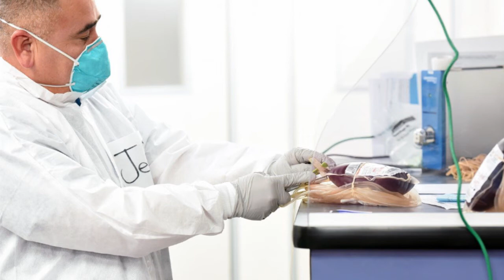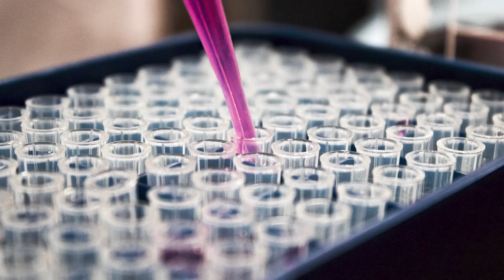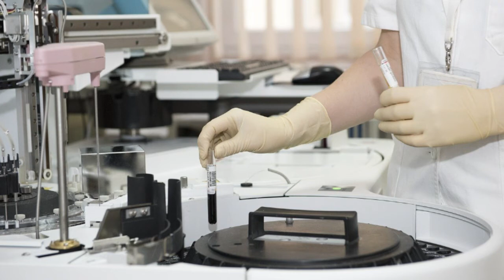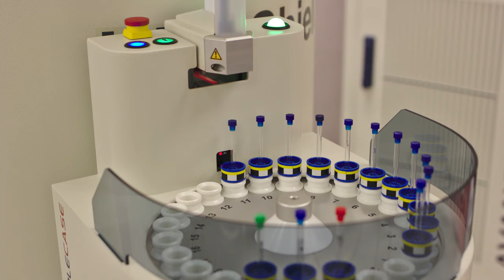Now many of the reagents are based on antigen-antibody reactions. Reagent storage temperature is very important. Frequent thawing and freezing decrease the potency of antigens and antibodies. Onboard reagent stability. The open reagents and loaded reagents in the instruments have very short stability as they are exposed to atmospheric air and frequent pipetting by manual method or the reagent probe that can contaminate the reagent. Please follow the manufacturer's stability instructions for onboard loaded reagents.